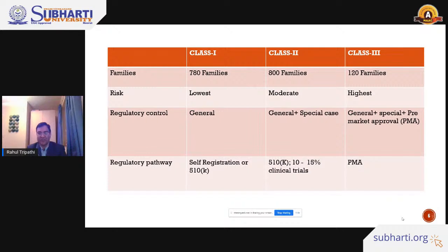Now the class 3, which is the highest risk class. The FDA gets involved with class 3 because that's the highest risk class to the consumer, and that's why the FDA most of the time comes into the picture. It's a highly regulated class of medical devices. Its regulatory control is general plus special control, and pre-market approval is needed. Pre-market approval is the case where the pharmaceutical industry needs to register their products before commercializing any products. This is also true with this class of medical devices, class 3. So pre-market approval, PMA, is needed from the FDA if you would like to commercialize your products.